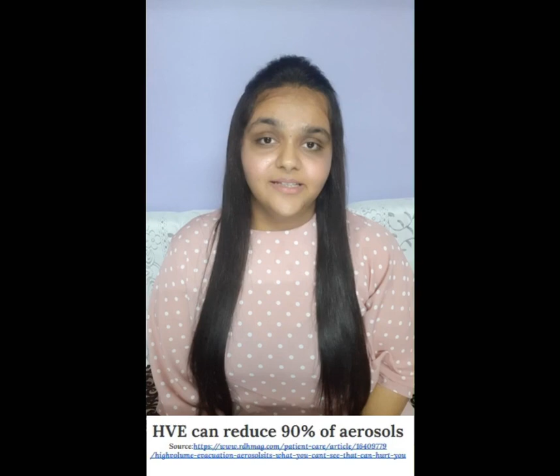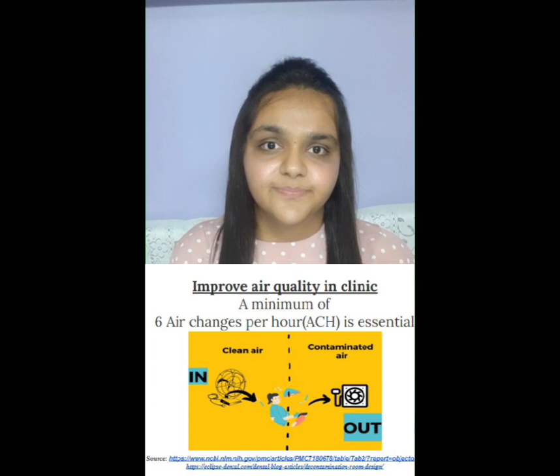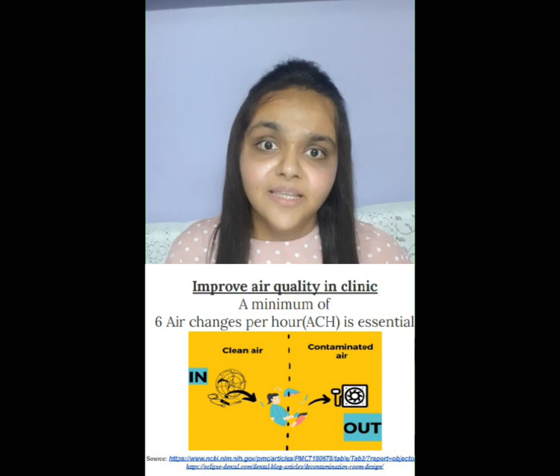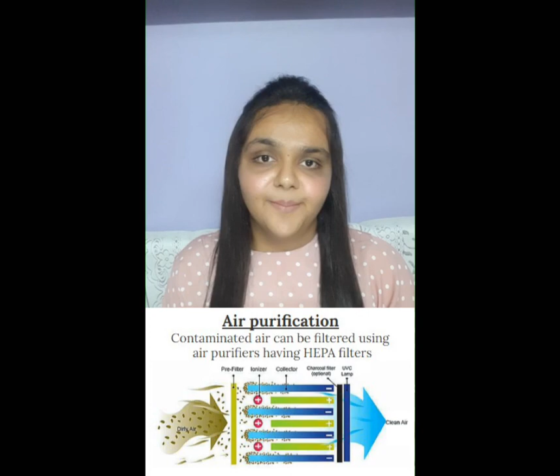Secondly, to improve the air quality in a dental clinic, a minimum of 6 air changes per hour is essential. So, the ventilation system should be designed such that the fresh incoming air mixes and dilutes with the contaminated air, and the mixture is then removed with the help of an exhaust system. Thirdly, air filtration can be done by using an air purifier having a HEPA grade filter to filter out the contaminated air in the clinic.